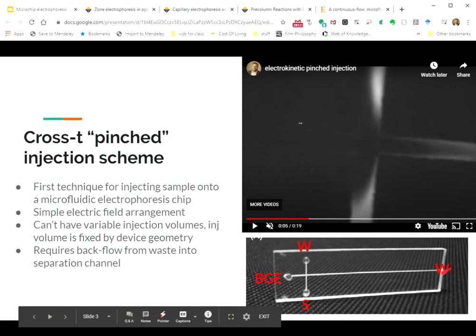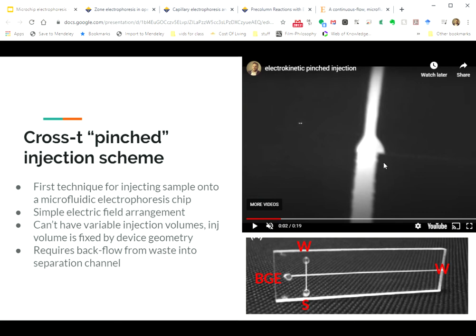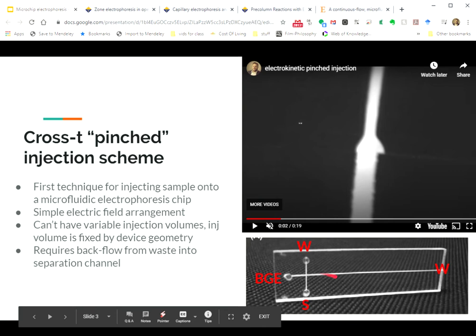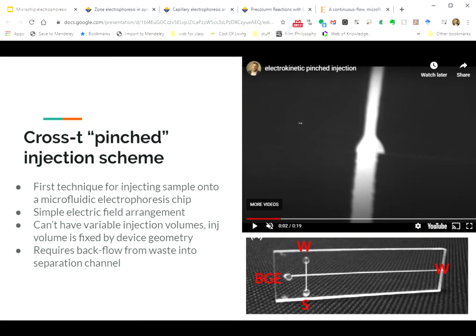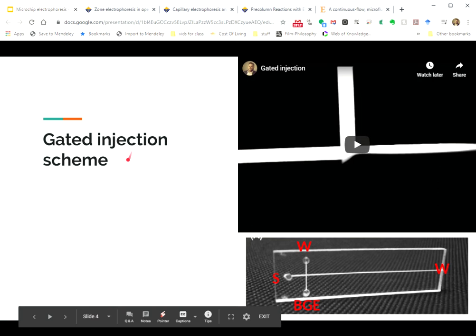There's a way to get it bigger. And the way you do that is by not having this cross T it's called an offset T. So we're flowing sample up here. If this channel was just offset a few microns this way, then what our sample would do to flow is it would come up here, it would turn the corner and it would go up that offset channel. And in that case you get a larger volume that gets injected as your injection plug. But again, it's built into the geometry of the device. You get one injection volume. That's not always ideal. Sometimes you want to change that up. The other thing is this pinched arrangement that I described to you when we apply a small voltage to pinch the flow to get these wings kind of limited in size. When we do that, we're actually, this is supposed to be a waste reservoir. This is where all of our, the outcome of all of our separations go after we're done with them.